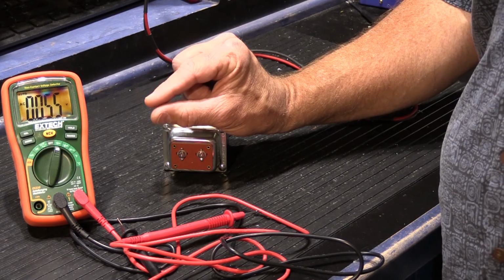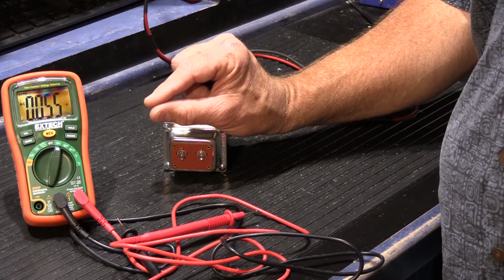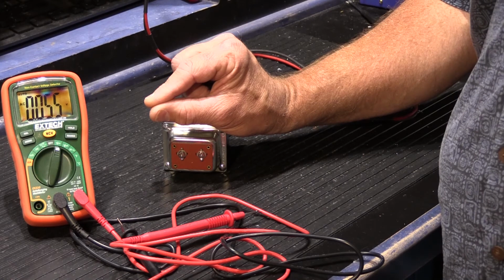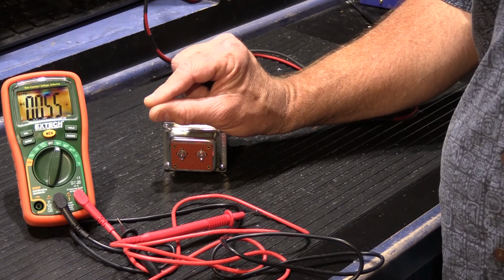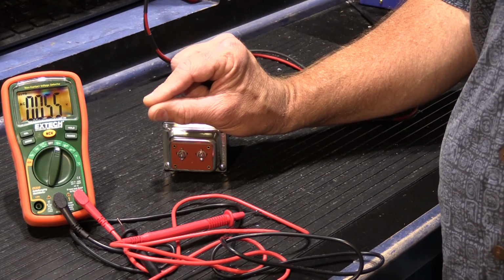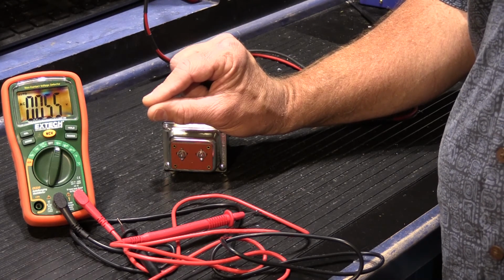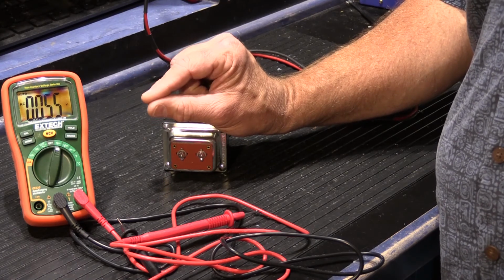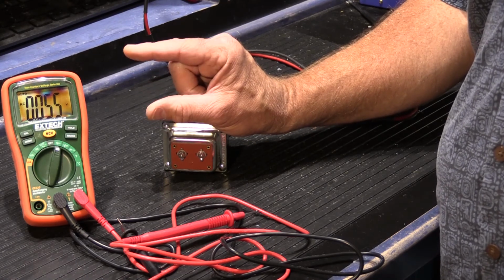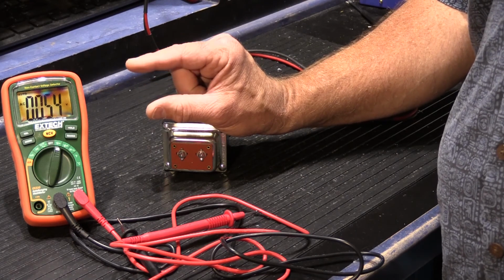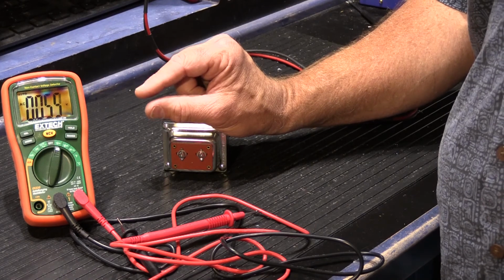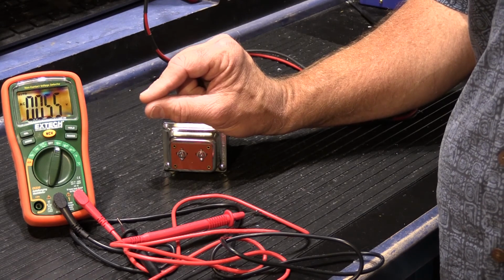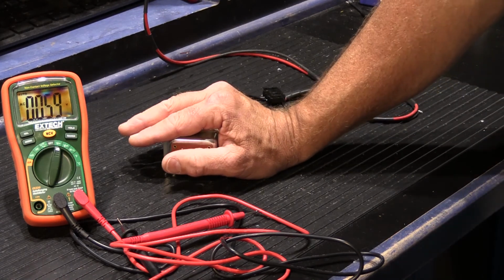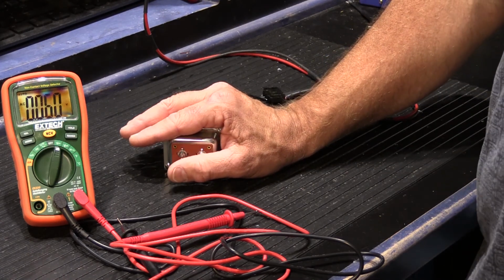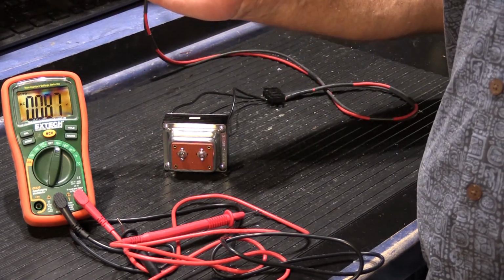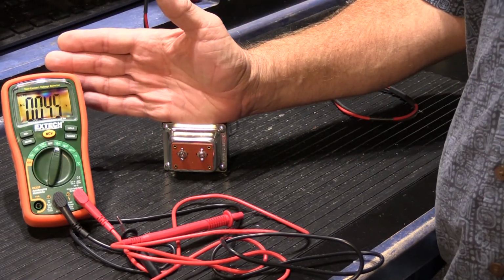This cycle will repeat endlessly until one of three things happens. You disconnect the device, the master station, from the intercom that's causing the overload. The intercom system dies altogether, so it's not drawing any power at all, or the transformer finally fails. So there will be times that the switch is opening and closing because the intercom is in such bad condition. This is a safety device that was put into transformers to prevent them from severely overheating and possibly catching on fire. These are called Class 2 transformers. As long as they're installed as per NuTone instructions, they are UL listed to be installed for the models that go inside the wall housing behind the master station.